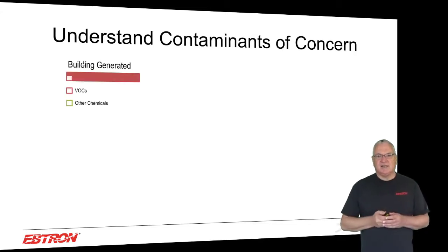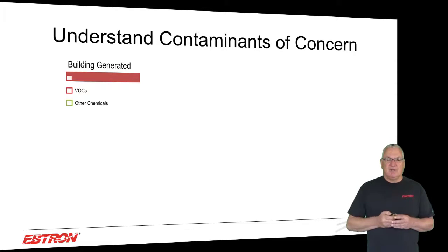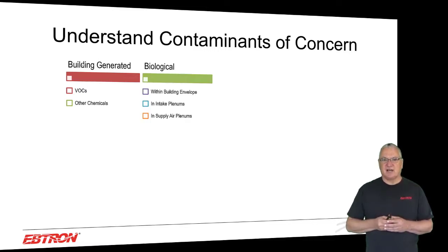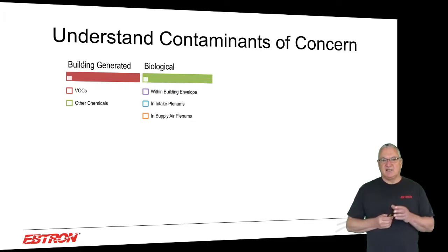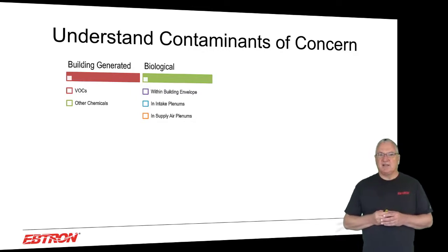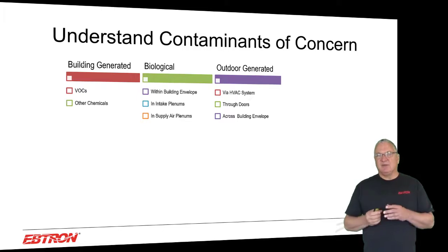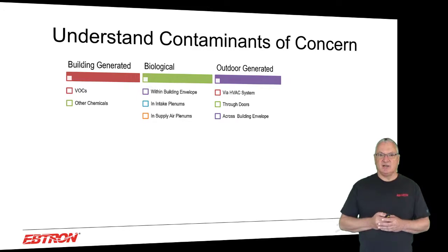When we drill down into the contaminants of concern, the building-generated contaminants are basically VOCs, but we can also have other chemicals. On the biological side, we can have contaminants within the building envelope, in intake plenums and supply plenums — until recently mostly moisture-based contaminants: molds and fungal growth. For outdoor-generated contaminants, we talk about entry via the HVAC system, meaning poor filter integrity, so we may be bringing in untreated outdoor air.